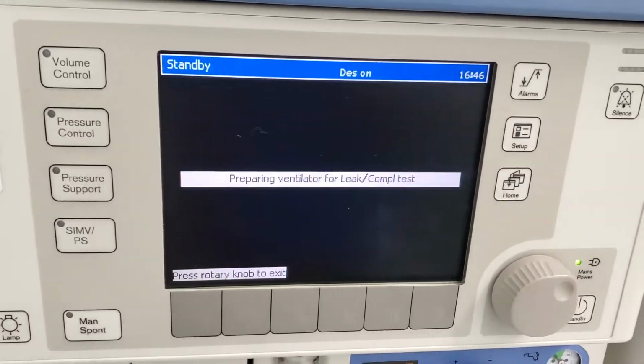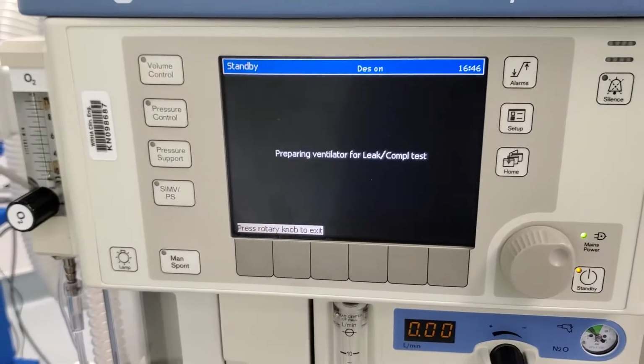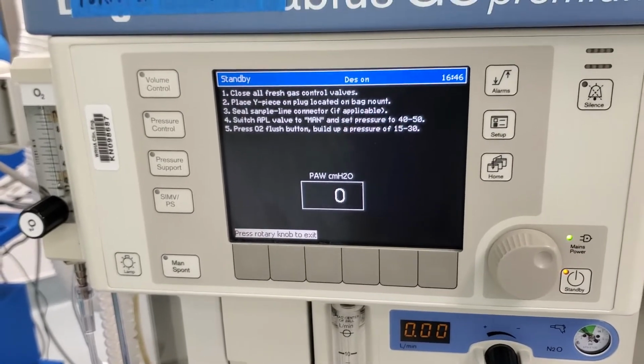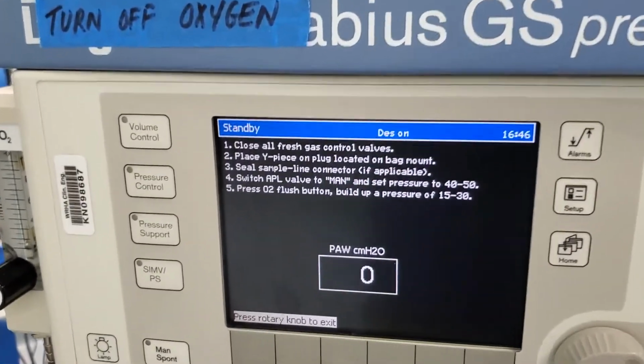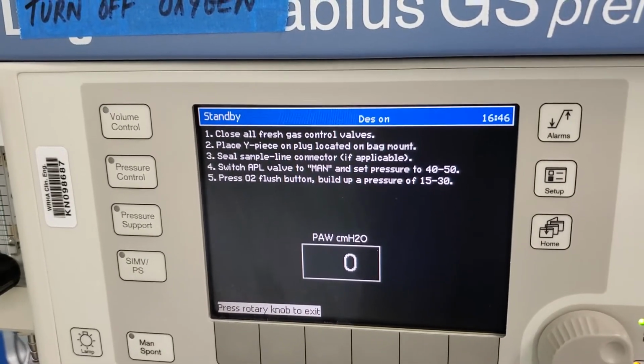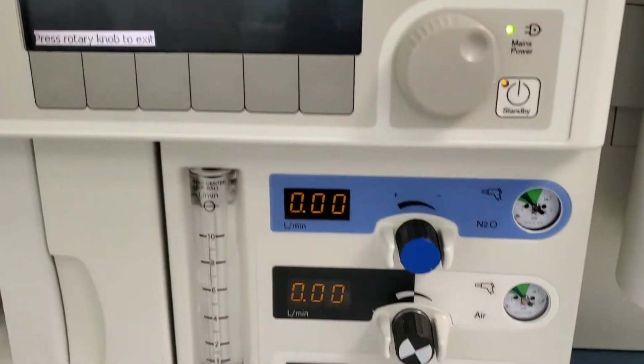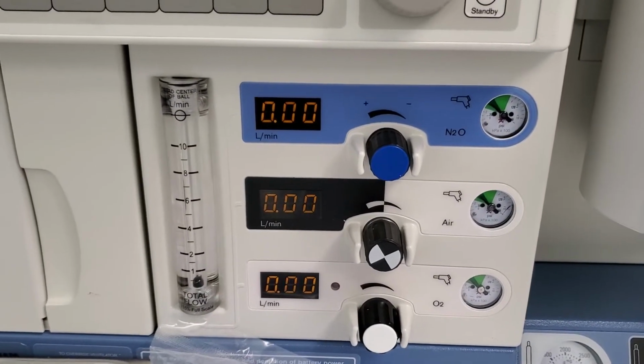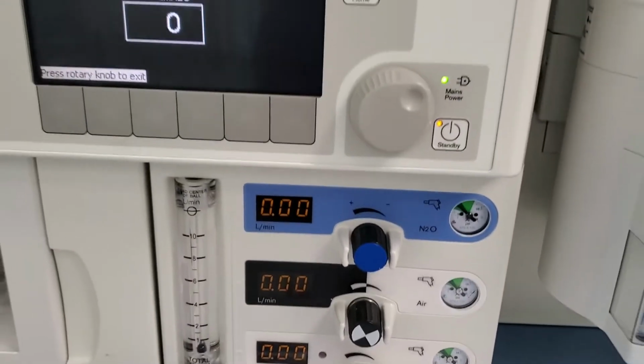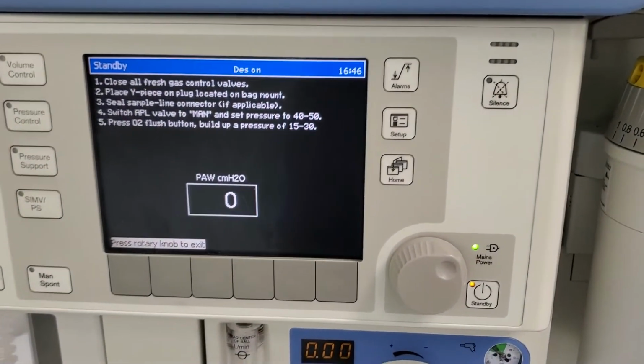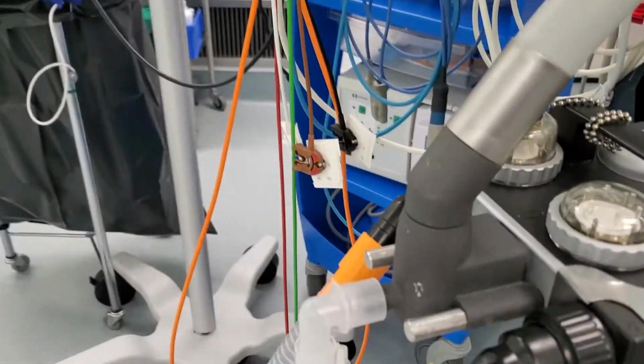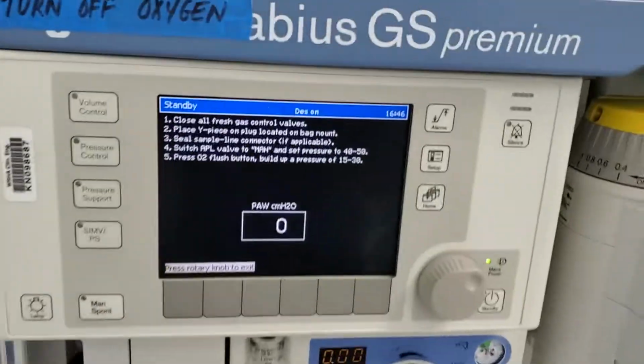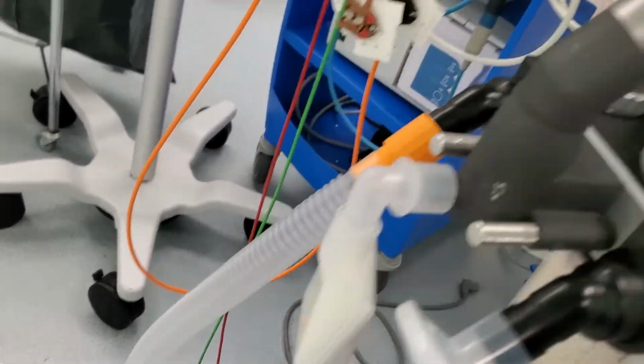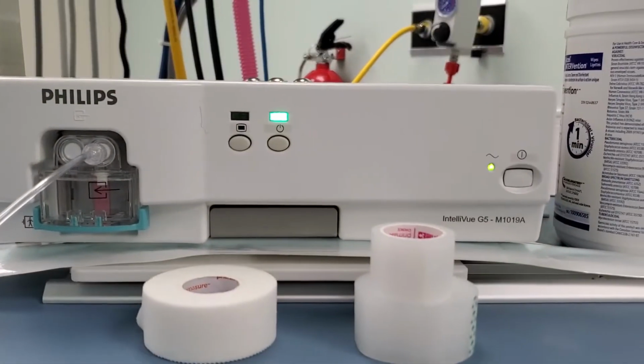The last test that we do is a total leak and compliance test. It's gonna make sure that there's no leaks in the ventilator and also measure the compliance of the disposable circuit. Again, the instructions to help you get through this test. We wanna make sure that all of our gases are off. If we had a gas flowing, it could compensate if there was a leak, and then we wouldn't know if there actually was a leak or not. We've sealed the Y piece onto the bag mount. The sample line connector, you can take the sample line out and seal that off as well.